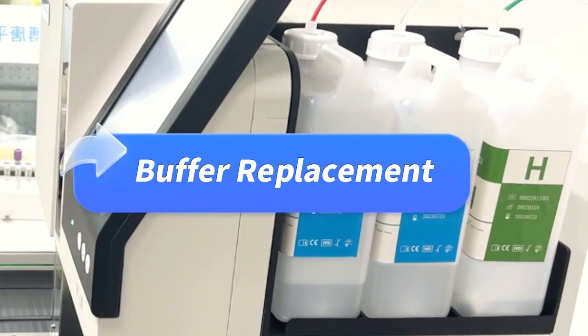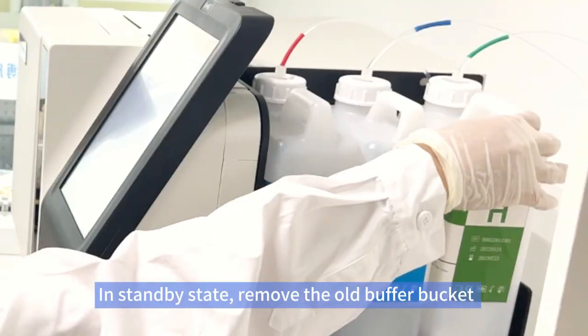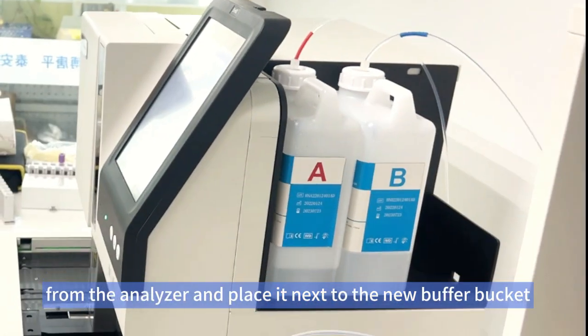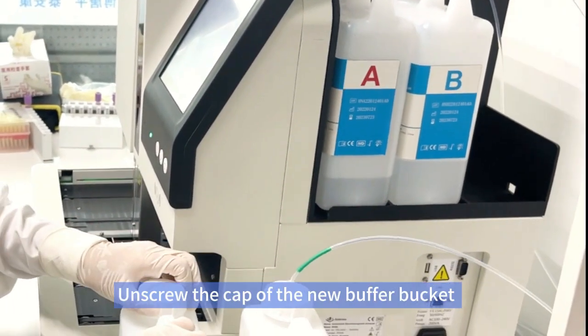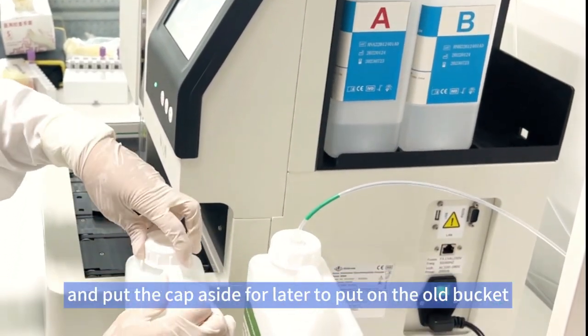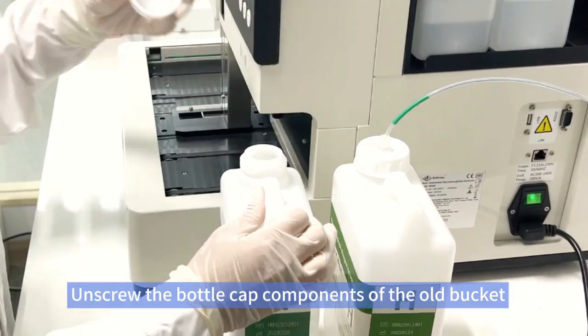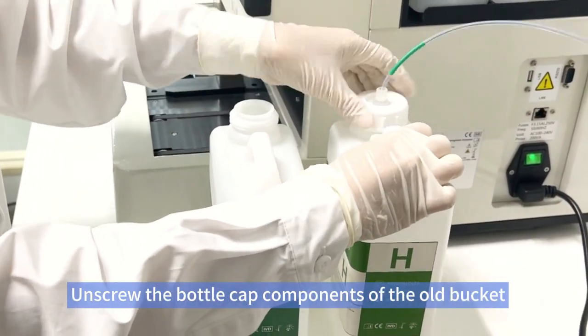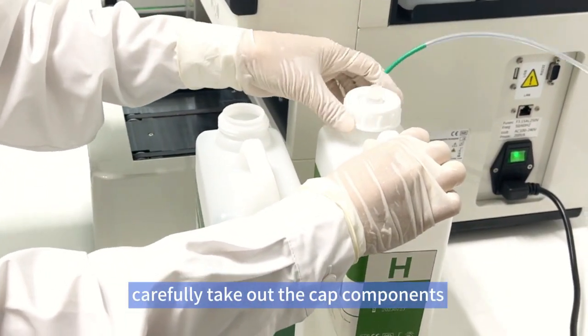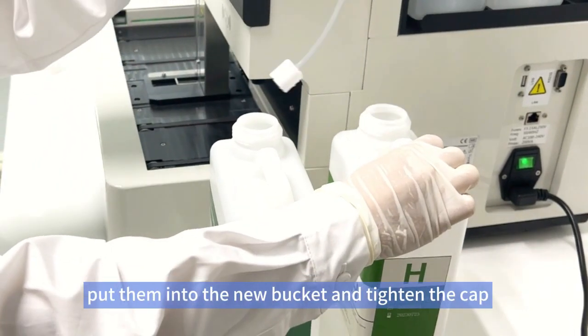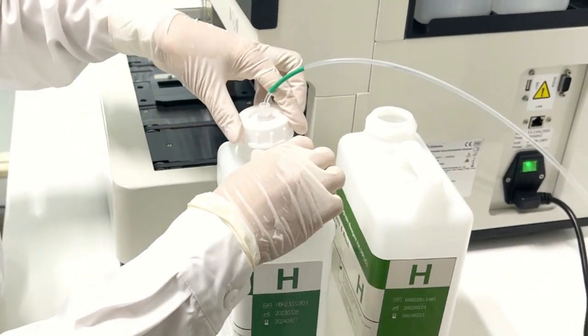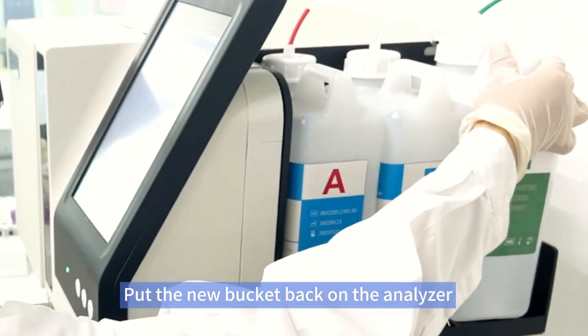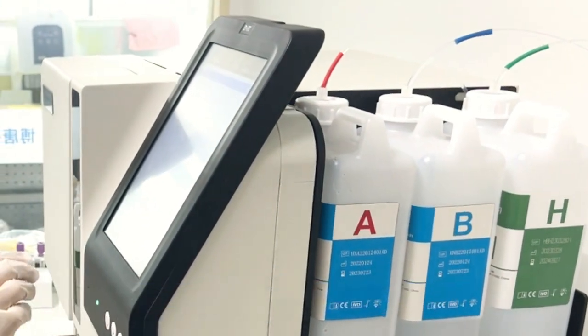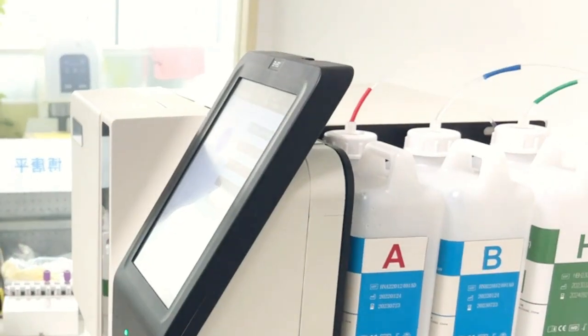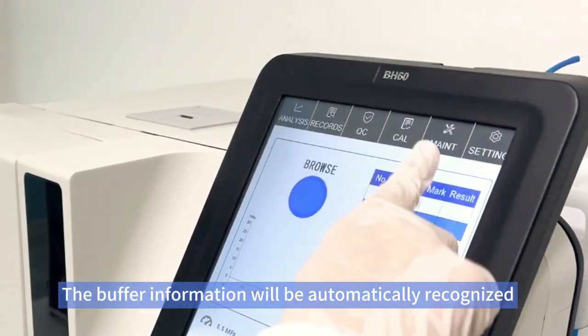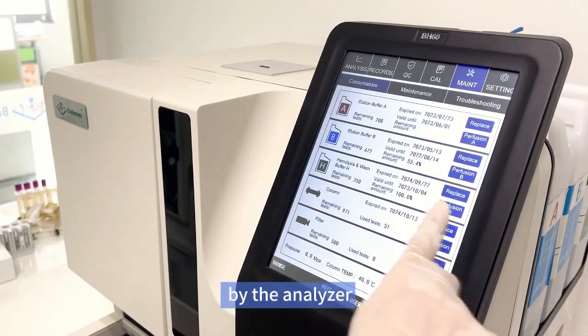Buffer replacement. In standby state, remove the old buffer bucket from the analyzer and place it next to the new buffer bucket. Unscrew the cap of the new buffer bucket and put the cap aside for later to put on the old bucket. Unscrew the bottle cap components of the old bucket. Carefully take out the cap components, put them into the new bucket and tighten the cap. Put the new bucket back on the analyzer. The buffer information will be automatically recognized by the analyzer.